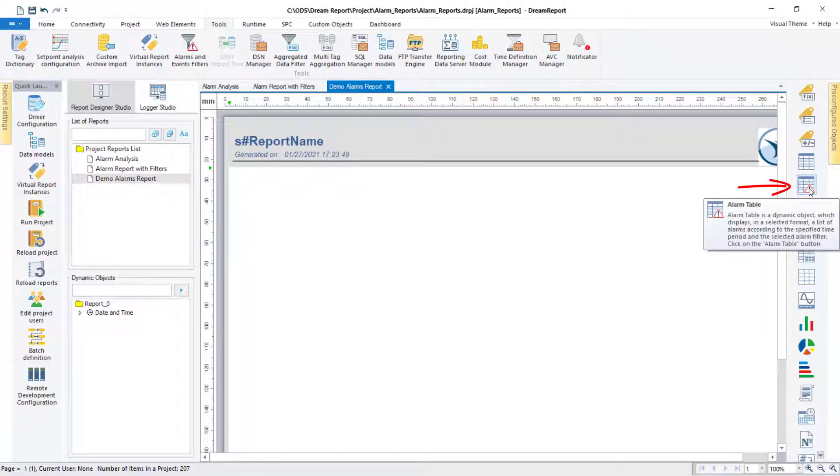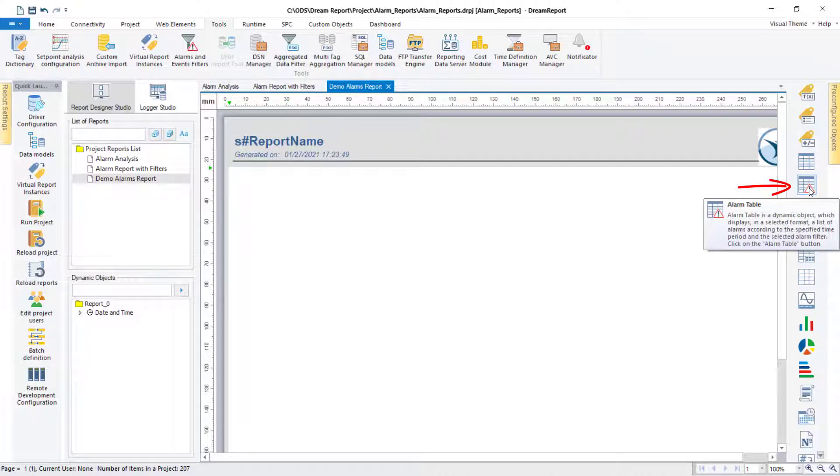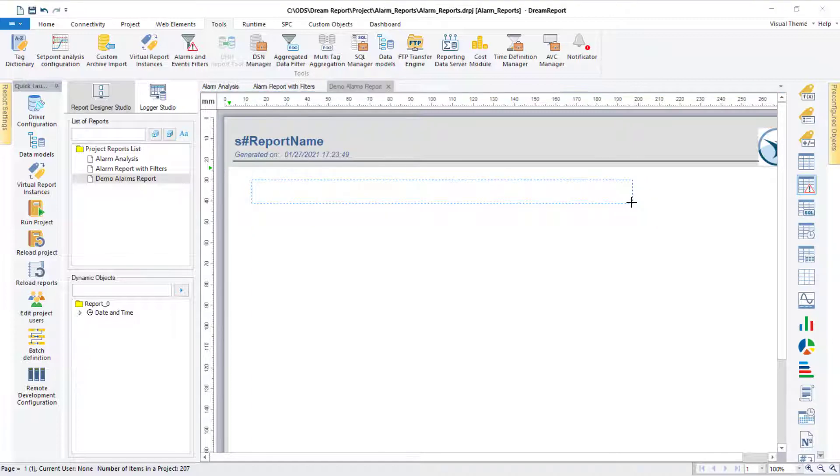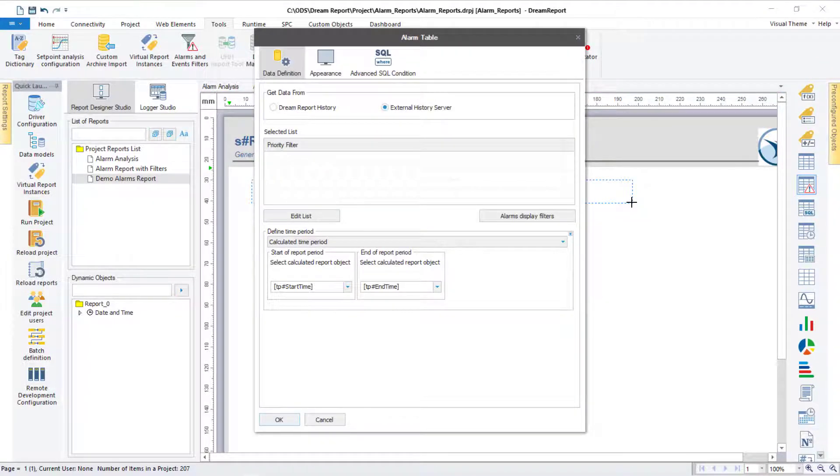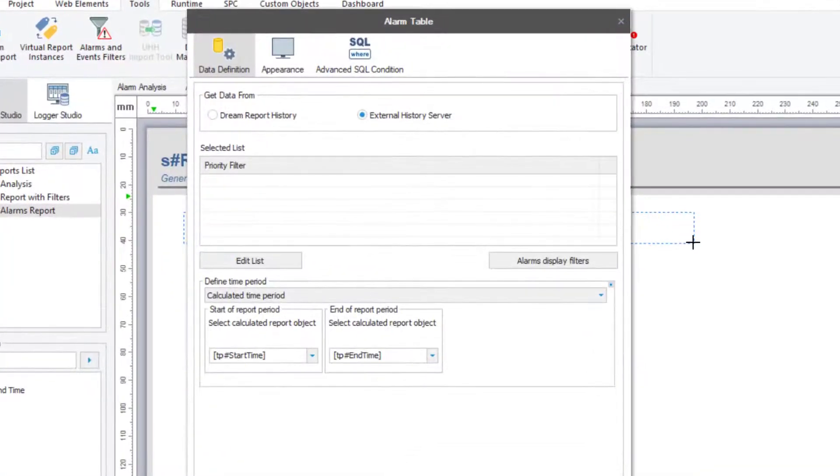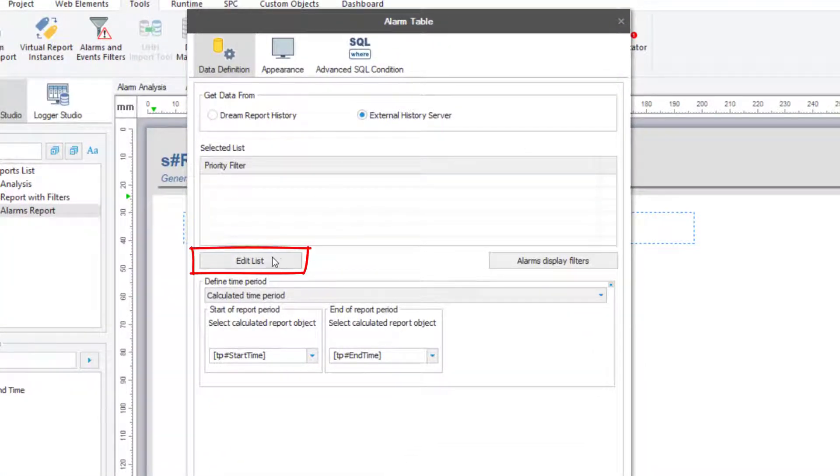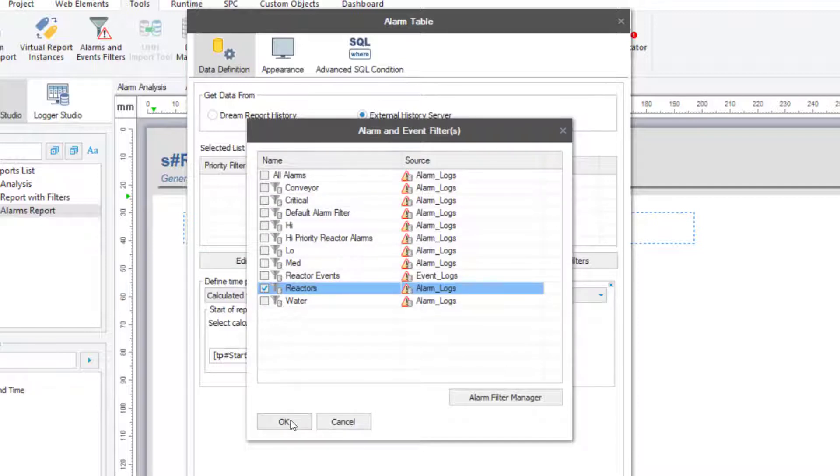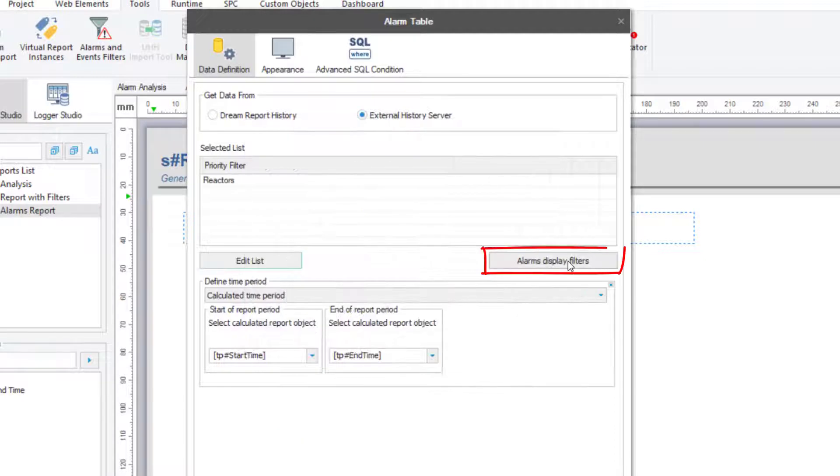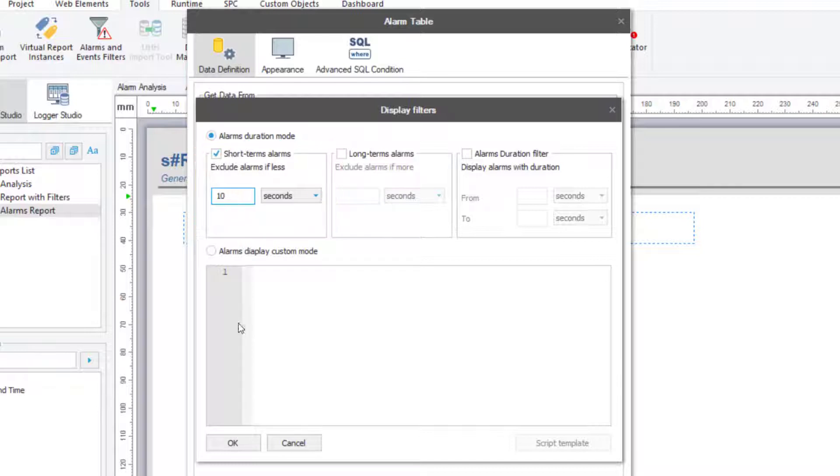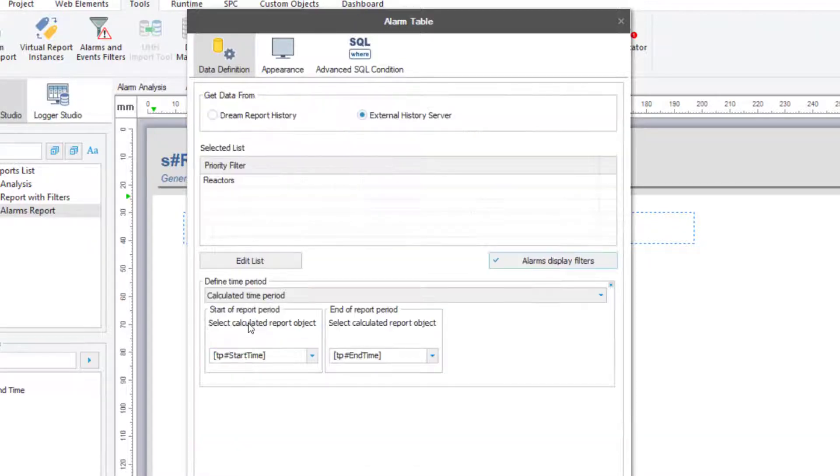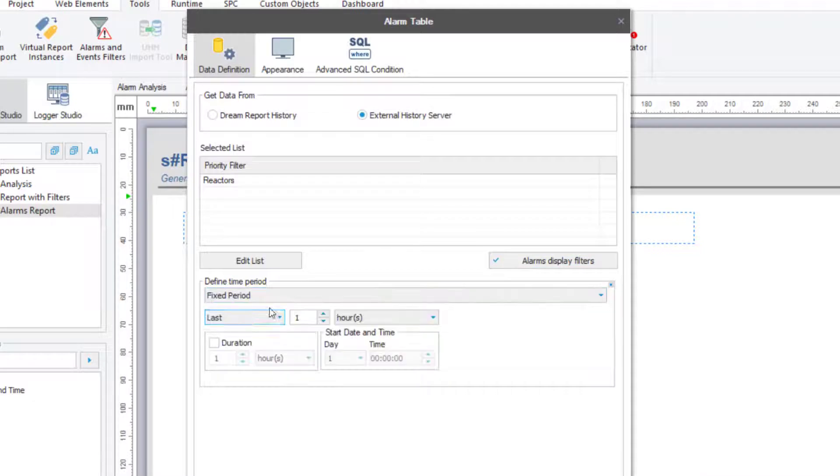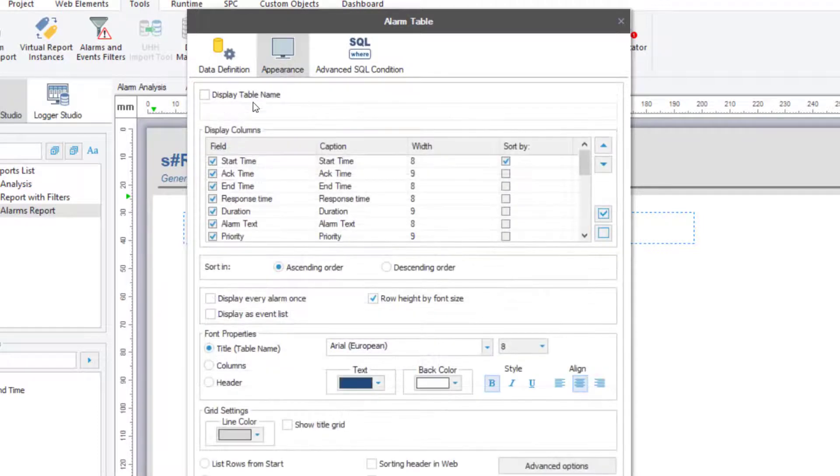In the new report, I'll start by adding an alarm table object. In this case, I'd like to roll up all alarms from my reactor alarms group by the number of occurrences of each alarm, but also to filter out short duration or nuisance alarms. I first need to select my alarm filters for the table, so I'll click the Edit list, and select predefined reactors alarm filter. Now let me exclude all alarms with a duration of less than 10 seconds. And then set the time period to be the last eight hours.